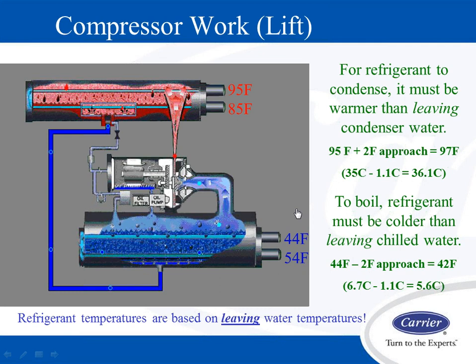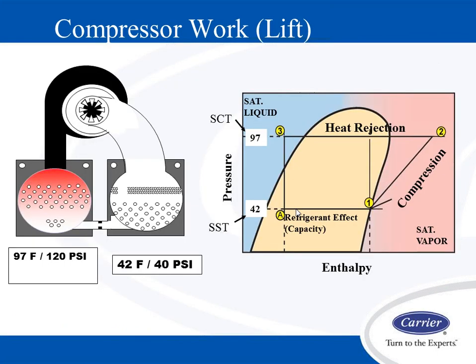That's what lift is. Someone may say we can operate with cold water, and the next question you should ask is, what is your leaving chilled water and what is your leaving condenser water temperature you need to operate that machine? Because it's leaving water temperature, not entering water temperature. When we look at this on a compressor map, a pressure enthalpy chart, at design day conditions we're operating at A1, and our lift is 97 minus 42. That's our lift on that machine.